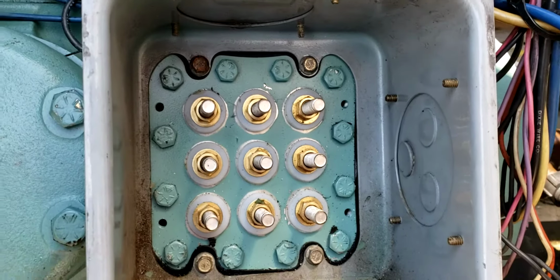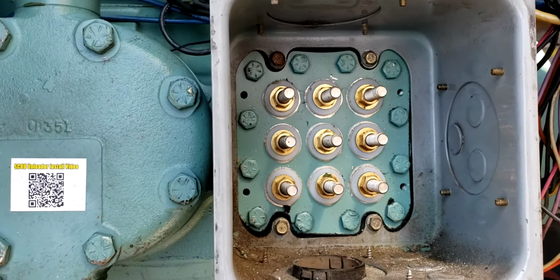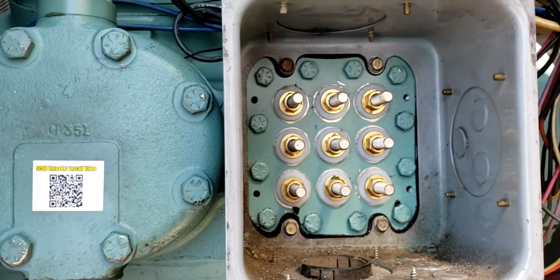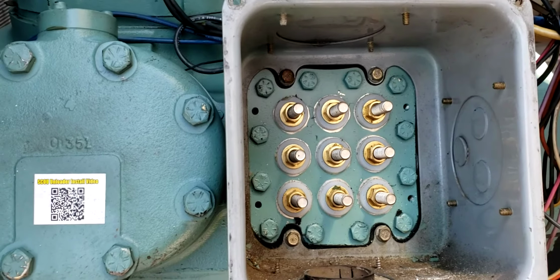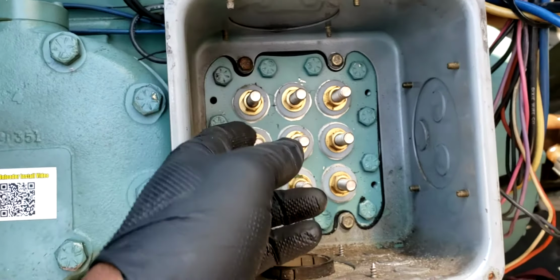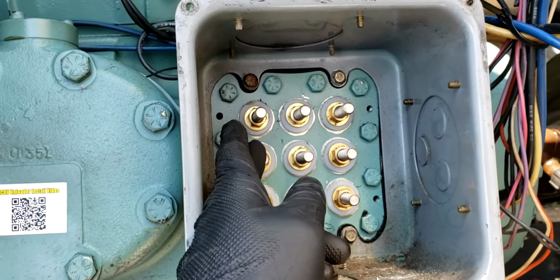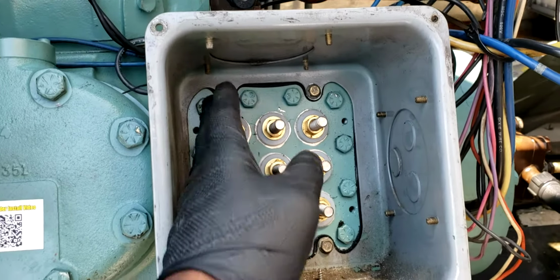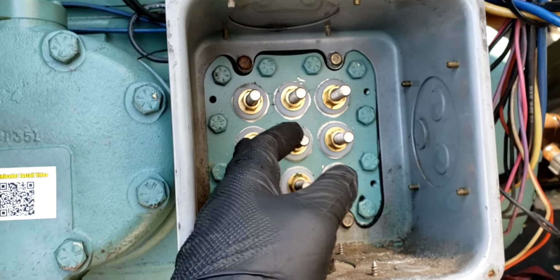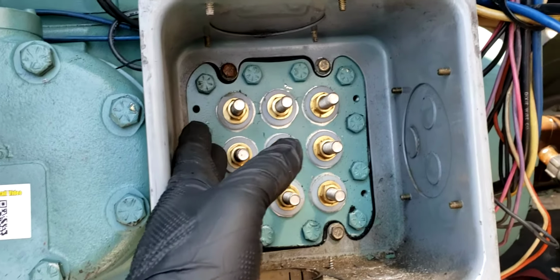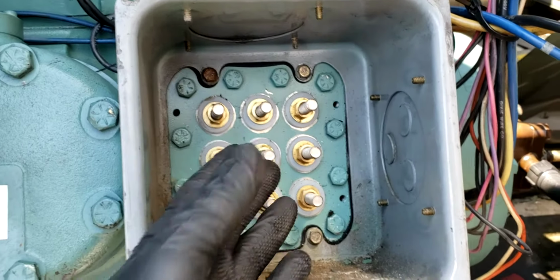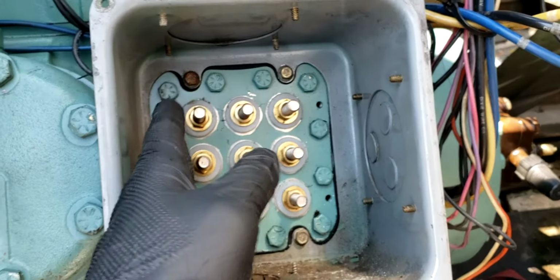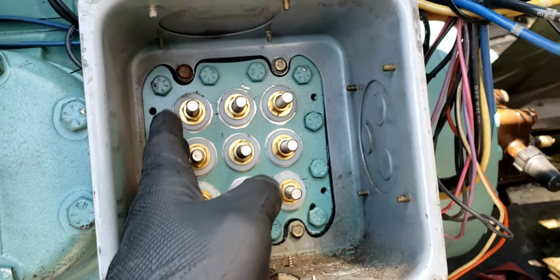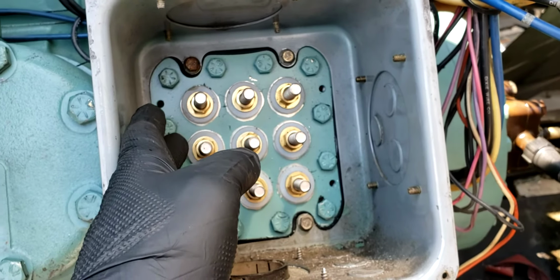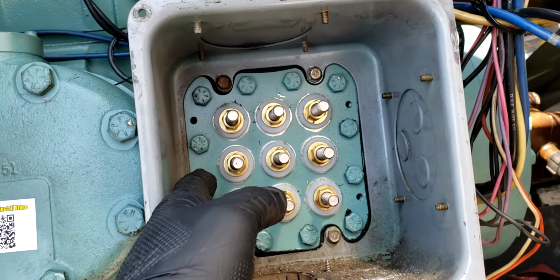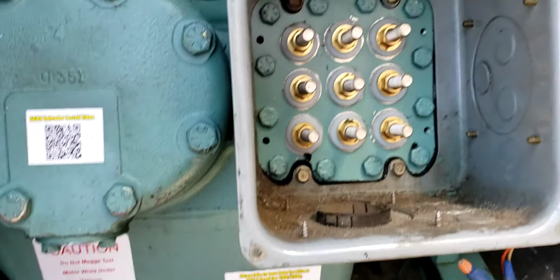Doesn't really matter the orientation, simply because this is a reciprocating compressor, and unlike a scroll, it's not rotation sensitive. You can just put it, line 1 down here or line 1 in the middle. It doesn't have to be properly lined up. And if you want to do it, you can, but for this compressor to operate, you don't have to have line 1 actually to the T1, and then line 2 to T2, and then line 3 to T3.